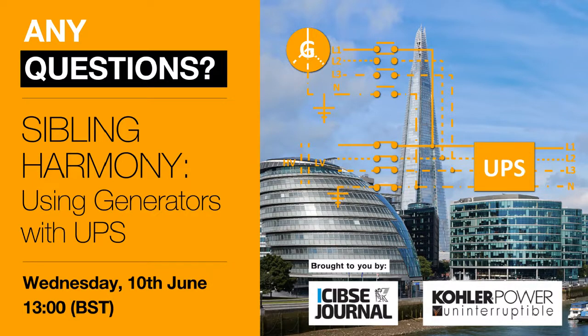Next question here from Nicholas, and Nicholas asks, do the fuel tanks fitted to the units, the skid of the units, require to be bunded? And if so, are they? Perhaps you'd explain what bunded means first as well. Yeah, it's a double-skinned fuel tank that if it decides to burst itself, it catches the burst into another lining. And then the legislation is anything above 200 litres, because an oil drum is 205 litres. Anything above 200 litres needs to be bunded, and yes, they are all bunded. Everything that UPSL install are bunded, and so are the fuel lines very often from remote tanks. Yes, everything is bunded. Okay, thanks for that.